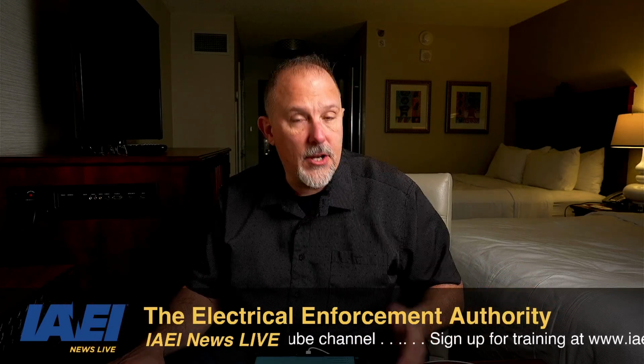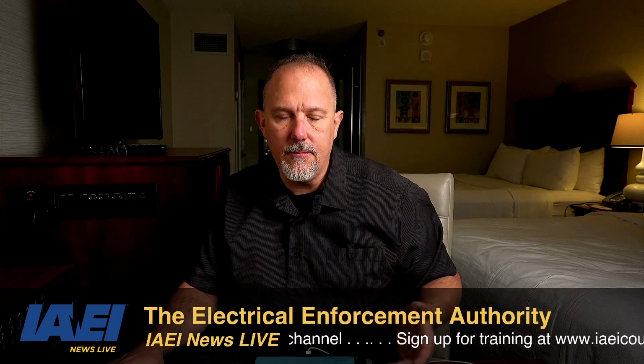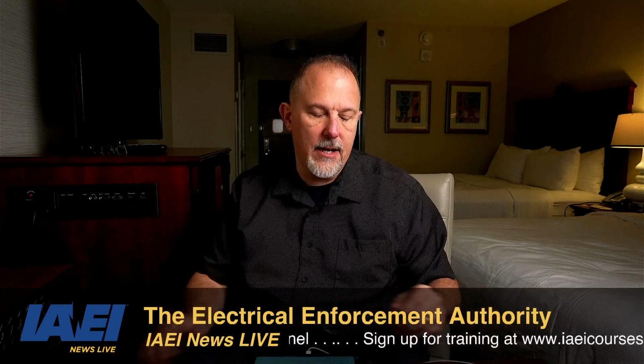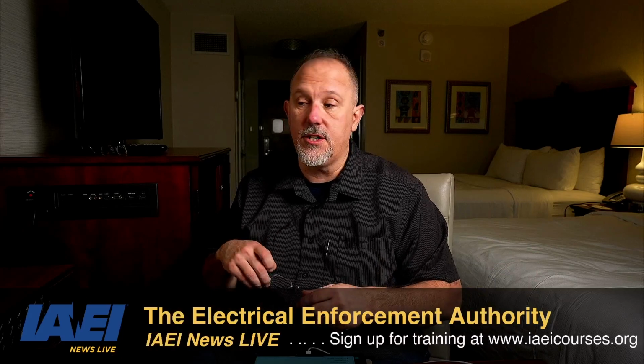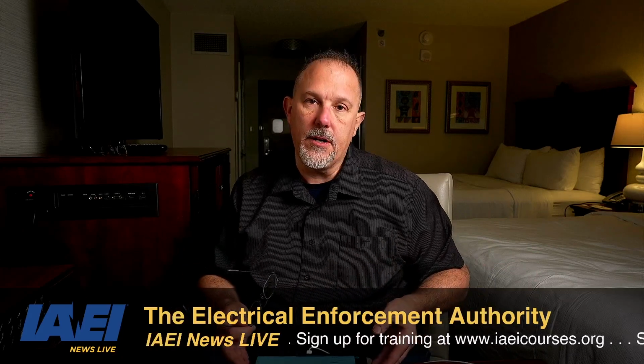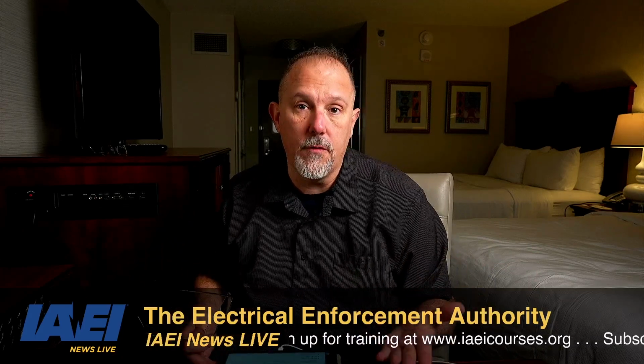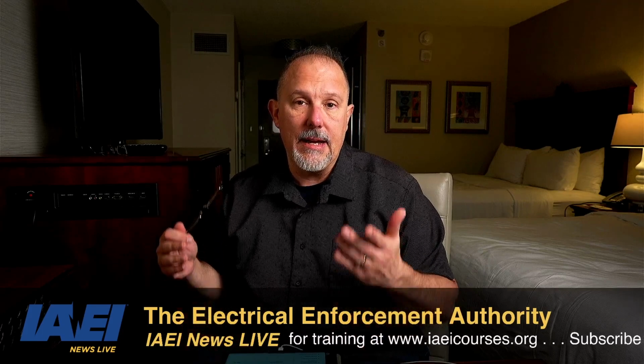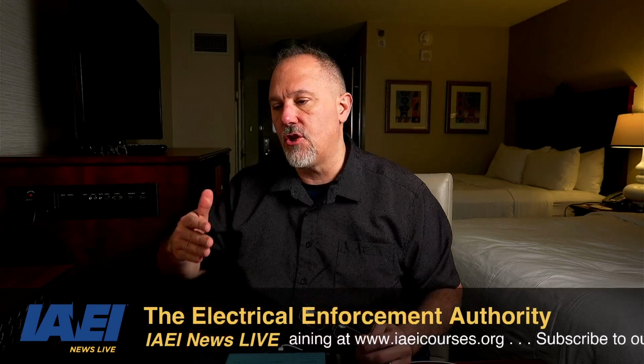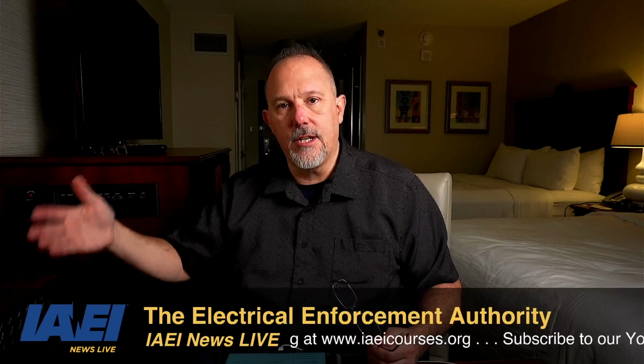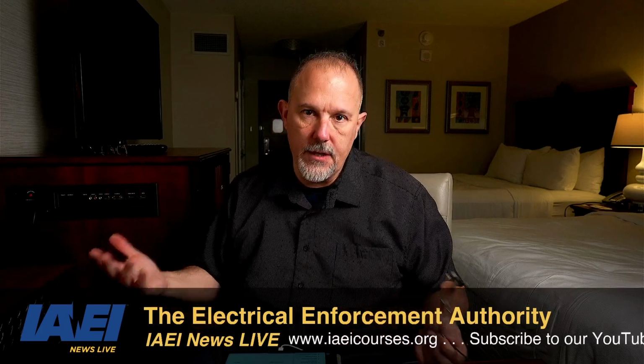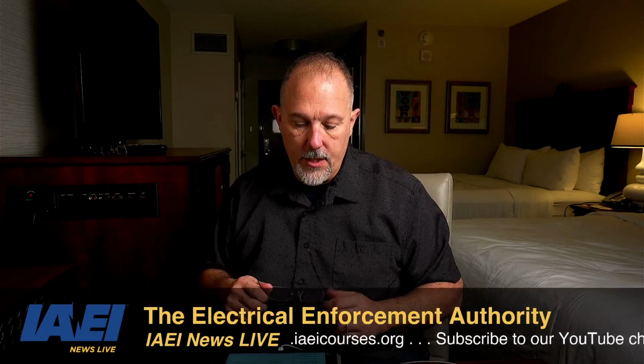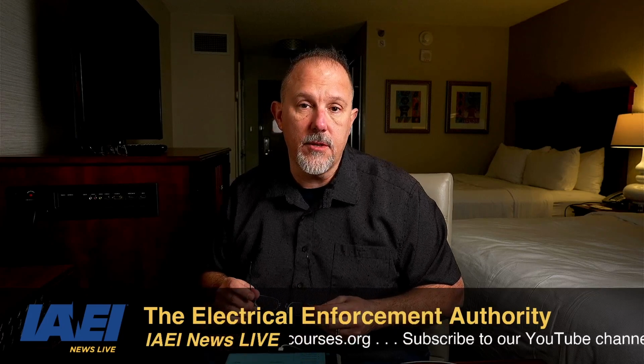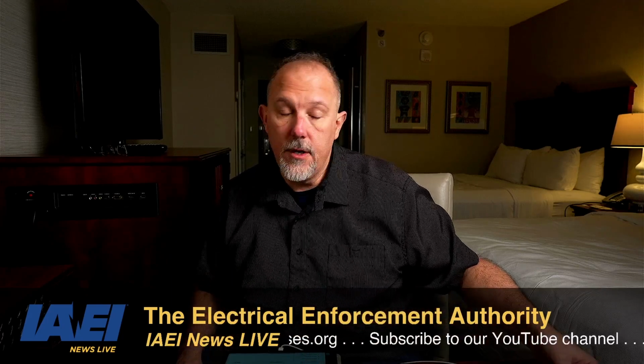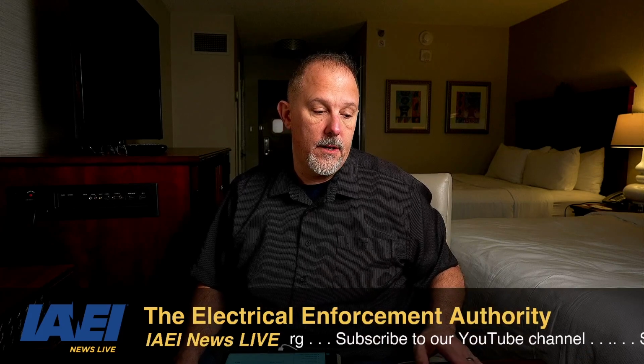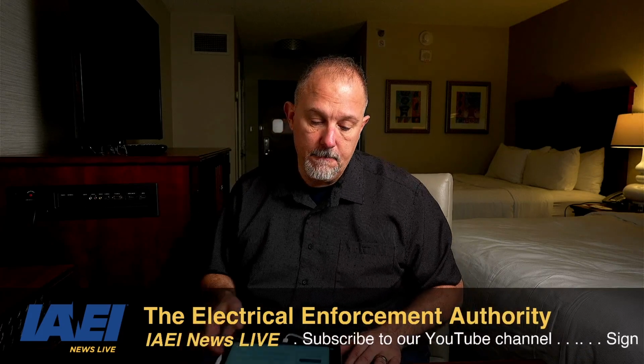And because you have a breaker inside for most cases, pretty much, I don't know about you, but all the generators I've seen all have a circuit breaker installed, or they'll have some sort of overcurrent protection as part of that generator. You just have to make sure I'm protecting those conductors appropriately, the feeder conductors. And we know that we can tap some of those, we can use the tap rules for those secondary conductors as well.